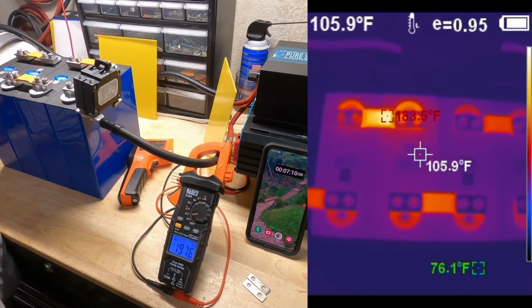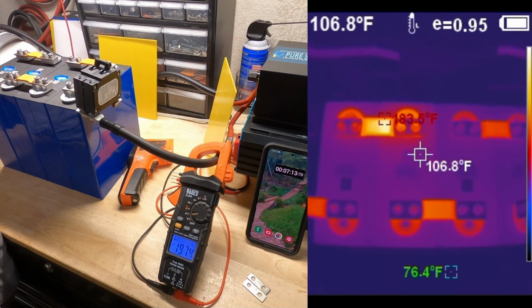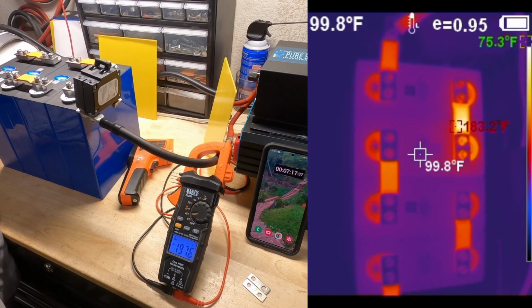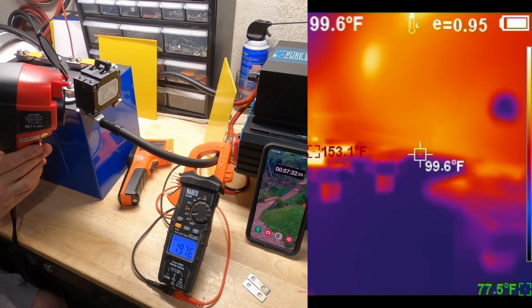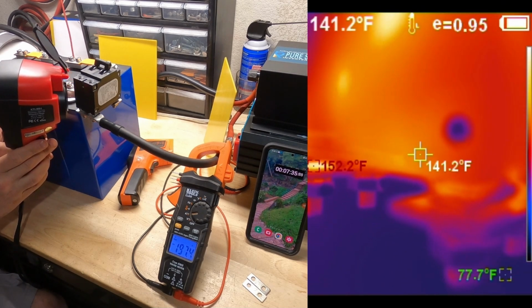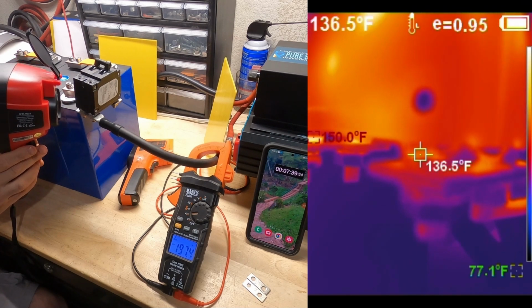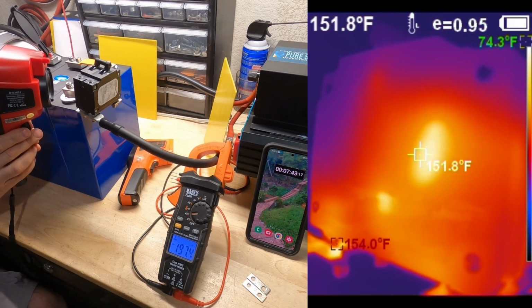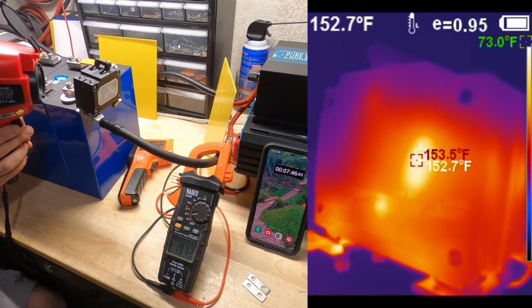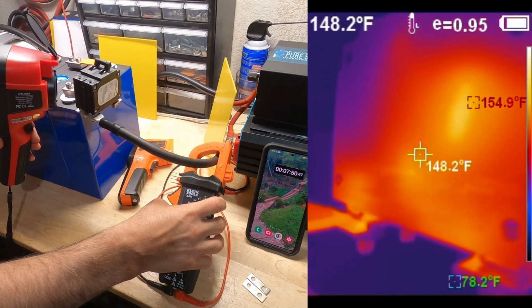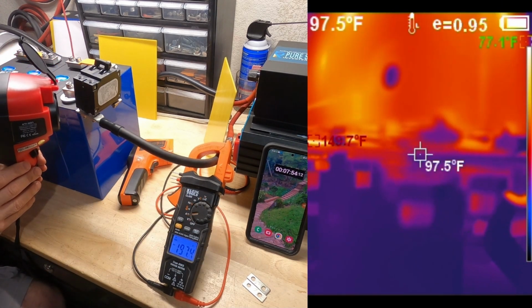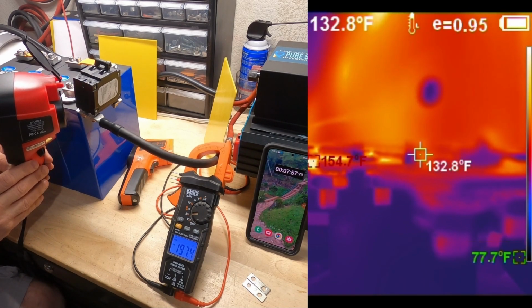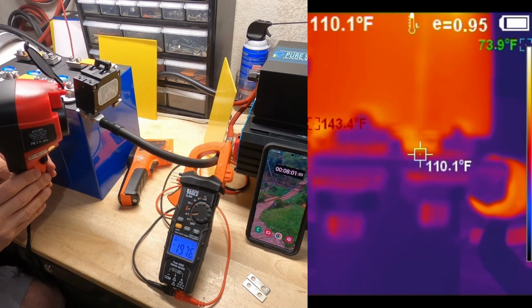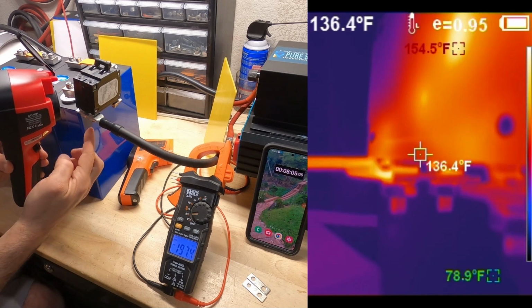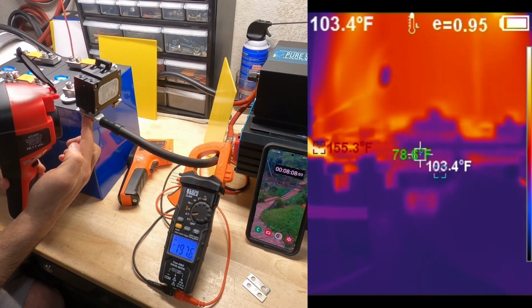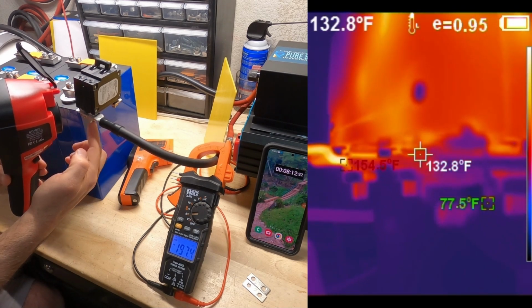Let's take a look at our entire pack again. Yeah, that bus bar. That one right there. Look at that thing. Let's take a look at our breaker again. We're at 7 minutes, 40 seconds. The side of the breaker there is 150 degrees. But as far as the contact terminal goes, it looked like a significant improvement there. I can just see the color profile there. You can see the lug, the double lug right here. This is pretty cool. You can touch that, no problem. Just about 90, about 100 degrees right there.